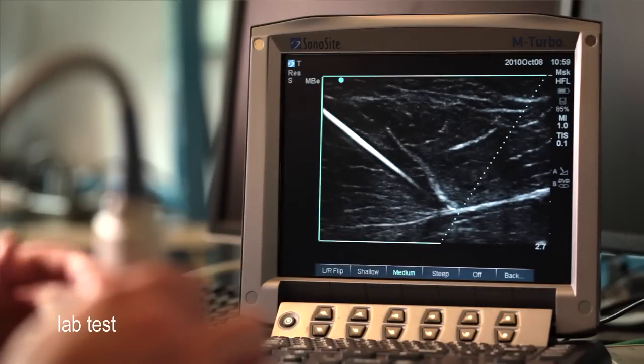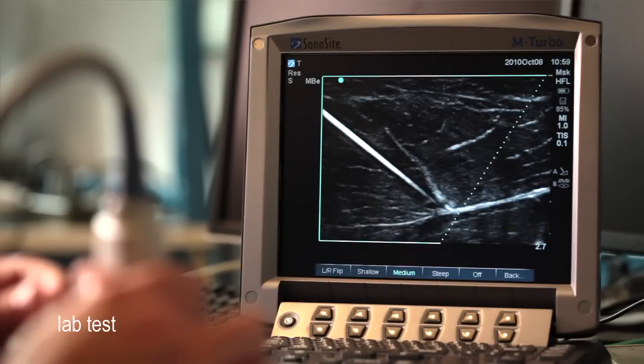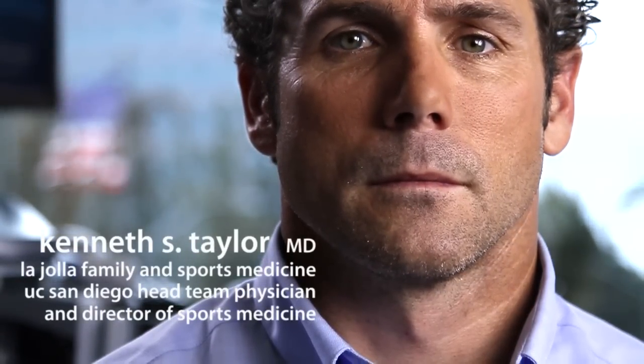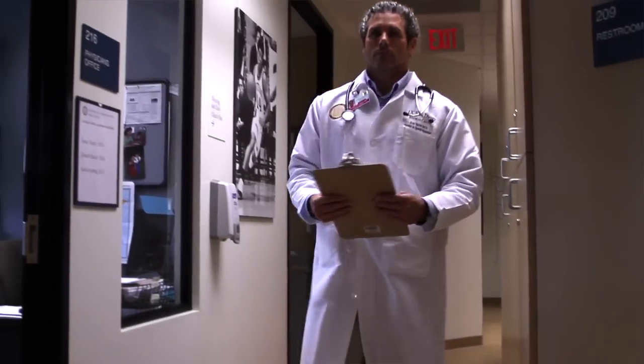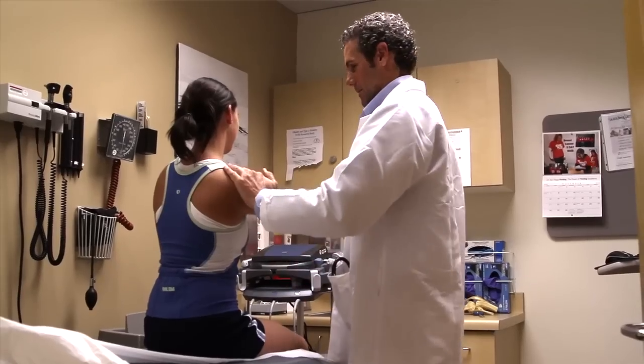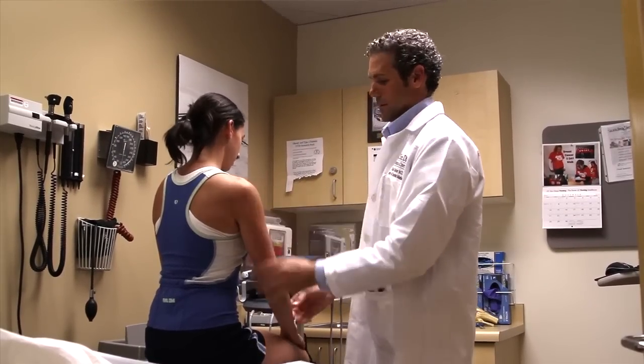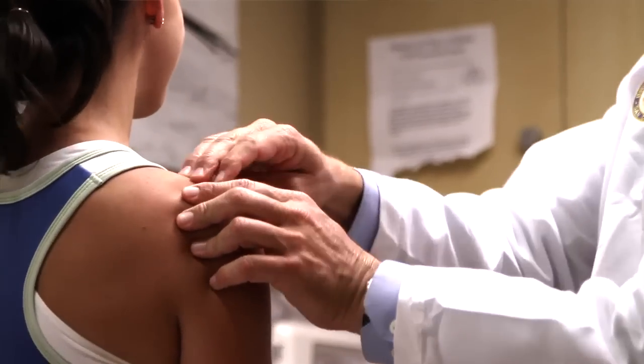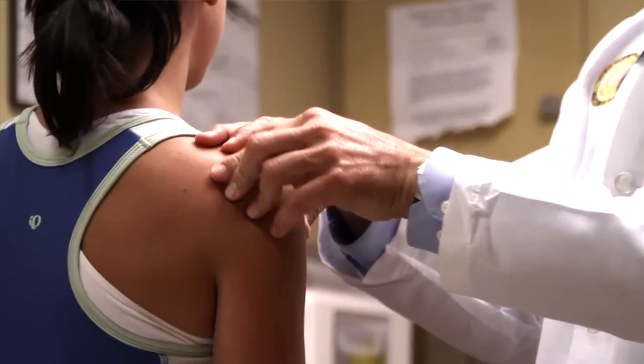As soon as we turn on the function of the advanced needle visualization, the image quality stays the same and we just see greater echoes when we insert the needle. I haven't noted any decrement to the image resolution and quality. In my practice, it's really added increased speed — I'm getting to the target more directly with less time, getting in and out, which always makes the patient happier and certainly reduces the amount of pain involved in a procedure.